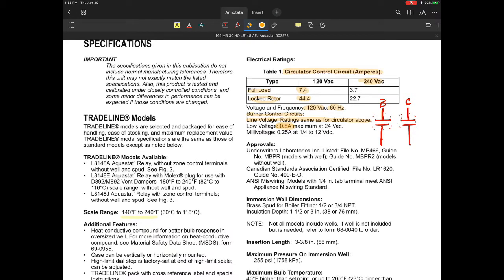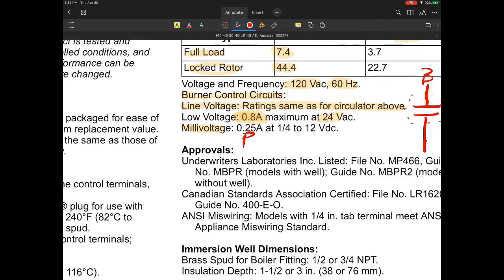So this actually will be fairly important to recognize, 0.8 amps max, because that might be what they're using to power some auxiliary type of relays. And that could be zone valves, as an example. So we're very limited on the number of zone valves we can actually use on some of these, depending on the model of the unit.